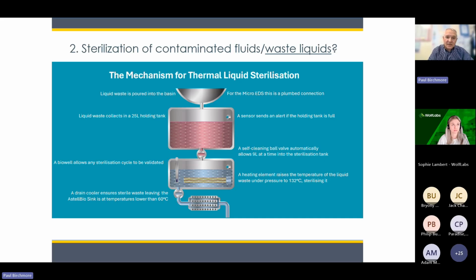The validation process for this one is we use a little cell. You can just see it in the corner there, a little probe whereby we have a sealed port. We put a little live bacteria module into there, and we will take that out at the end of a cycle, incubate it, check that the standard bacteria is killed, and now we've got a validatable process for ensuring that all the liquids in that process have been through the necessary high temperature part of the process.